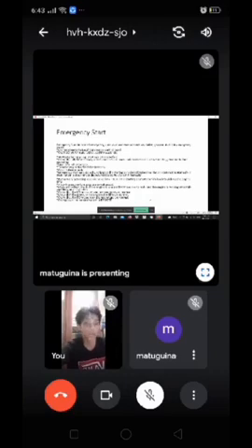Emergency start: in case of emergency, if auto start and manual start have failed, you can start it in emergency mode. Change remote to local from the engine control panel. Check LO, starting air, fuel oil, cooling water, etc. Start the LO priming pump 10 minutes before. Check all the necessary valves and lines are open and no interlock is active on the generator before operating. Open the indicator cock.